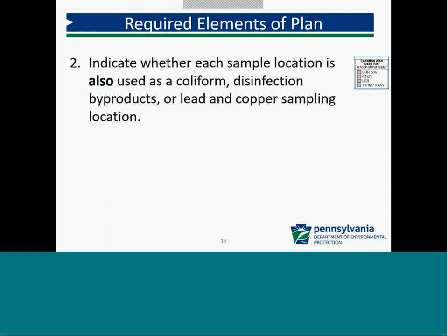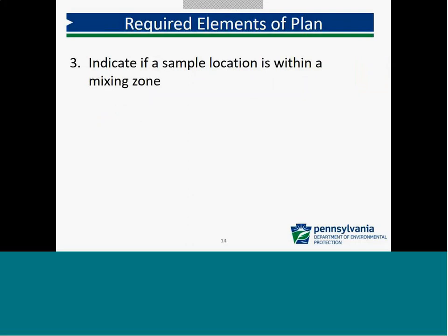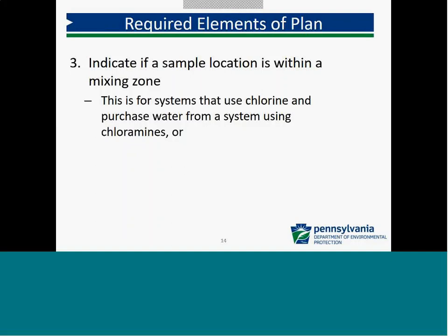Second required element of the plan is to indicate whether each sample is also used as a coliform, a disinfection byproduct, or a lead and copper sampling location, because some of these will certainly overlap.